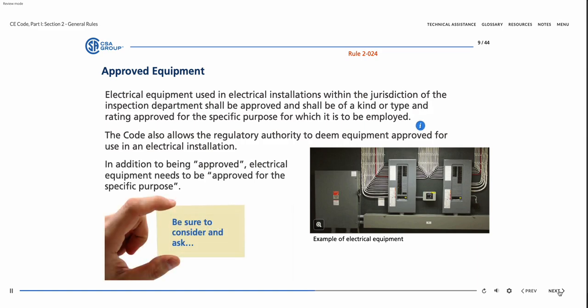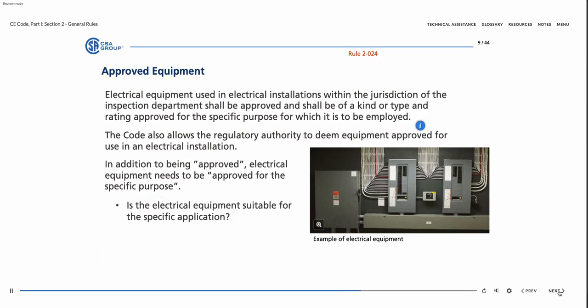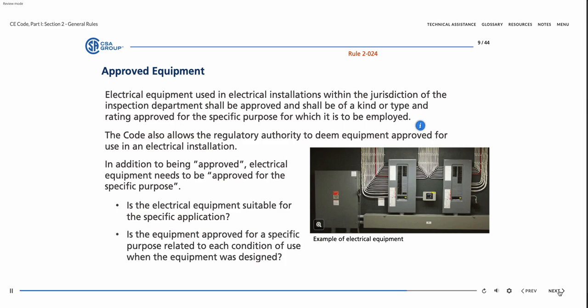In addition to being approved, electrical equipment needs to be approved for a specific purpose. For example, is the electrical equipment suitable for the specific application, including the appropriate application classifications, ratings, and characteristics? Is the equipment approved for a specific purpose related to each condition of use when the equipment was designed, constructed, tested, and approved for installation in accordance with provisions of the code?